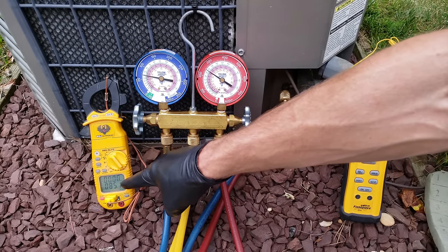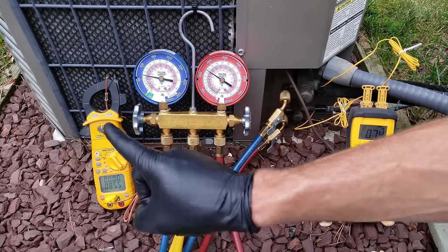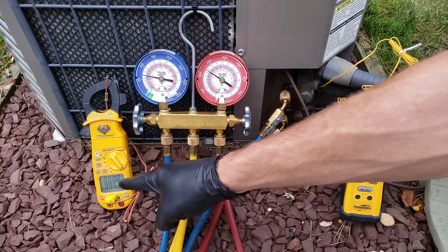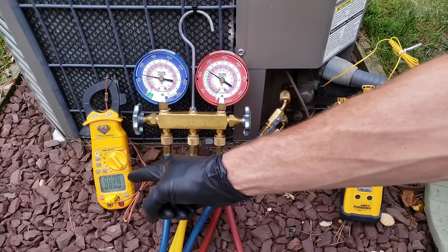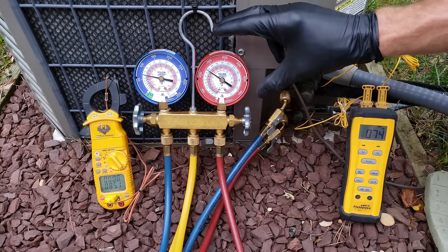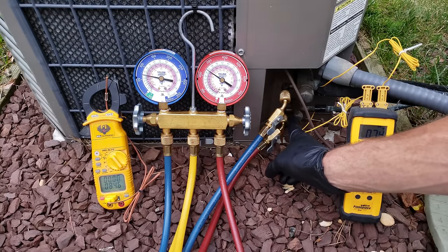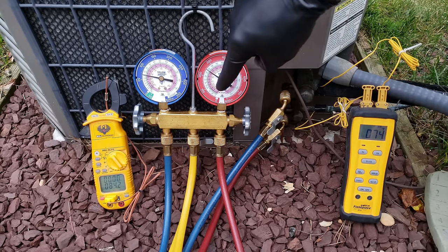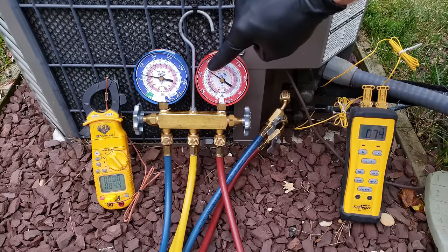We're reading 85 degrees outside right now — that's the air getting sucked into this coil and blown out the top. If you add 30 degrees to that, you're looking at 115 degrees as a target saturated temperature on your high side gauge. Right now we have our high side gauge hooked onto the liquid line, and the outer ring shows pressure while the green inner ring shows the R22 saturated temperature at any given pressure.